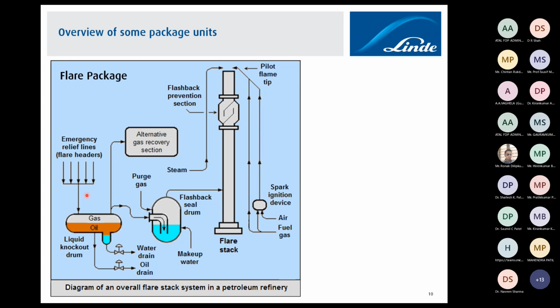Whenever, by virtue of operation, there is a high pressure or high temperature, the pressure safety valve will pop up, and all the liberated gases come to a common header. That liberated gas is hydrocarbon. We cannot leave it into the atmosphere. So it comes to a liquid knockout drum. Sometimes it is a two-phase flow, with some liquid droplets also carried along with the safety valve discharge. So we need to separate both phases, gas and liquid. The liquid phase goes back to the system, and the gaseous stream we have to feed into the flare stack.